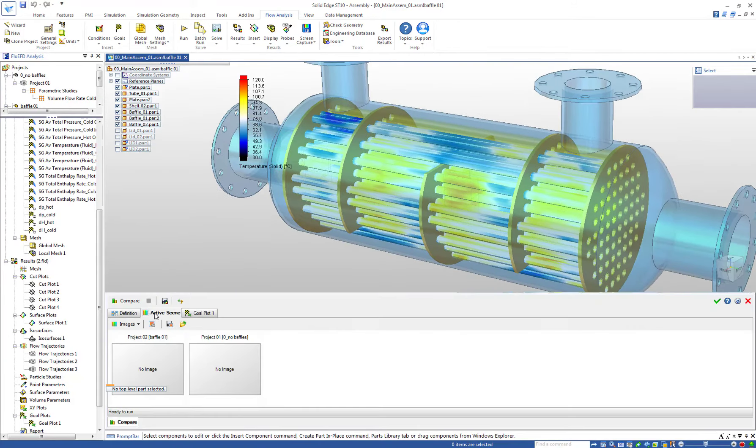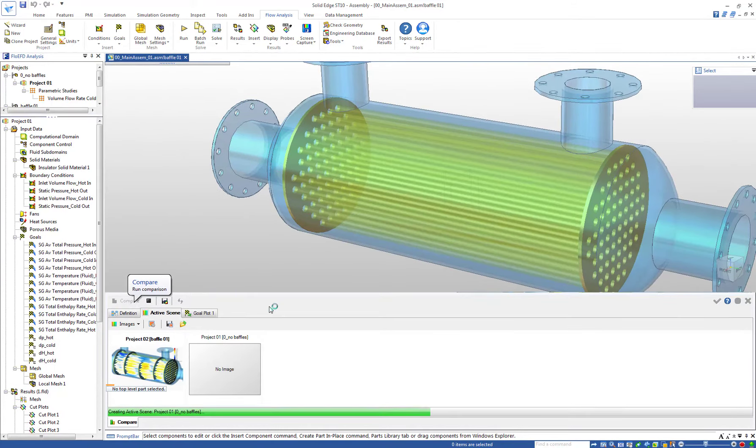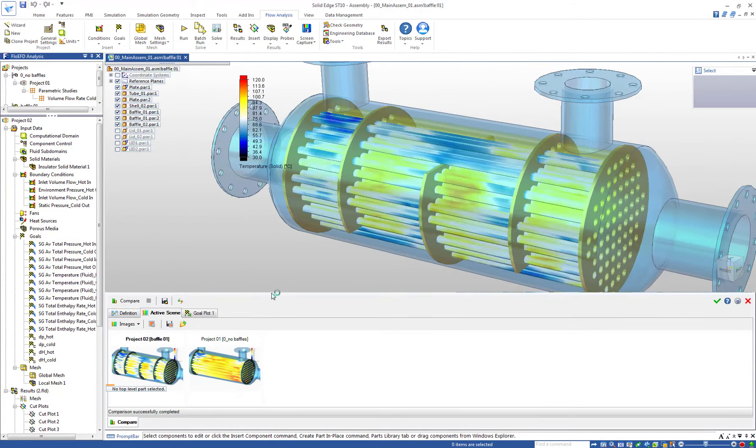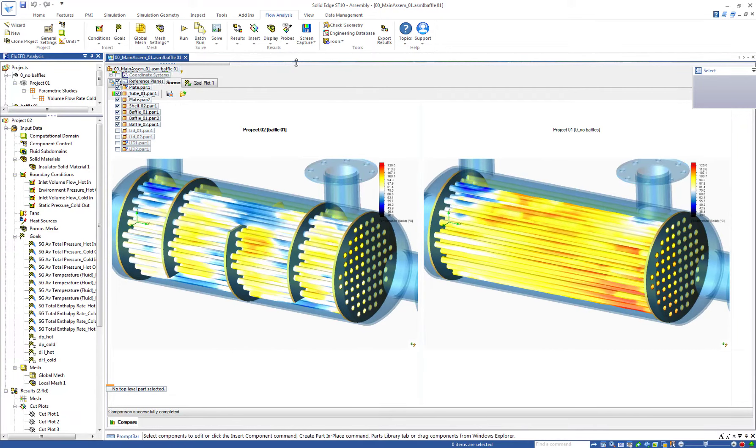The compare tool allows us to compare the results simultaneously, showing here the solid temperature on the tube surfaces, which seems to be more uniform for the version equipped with the baffles.